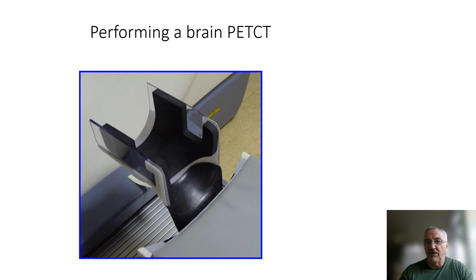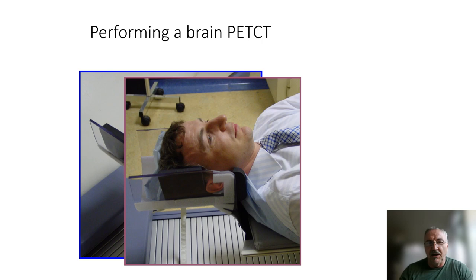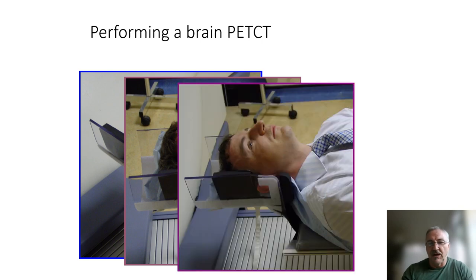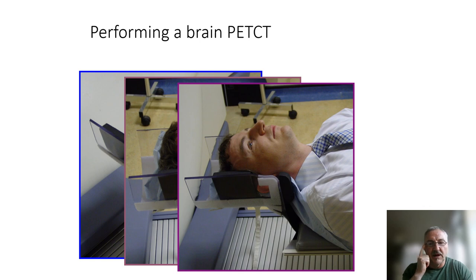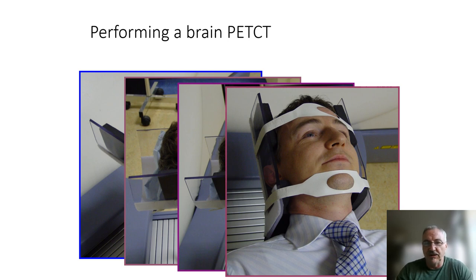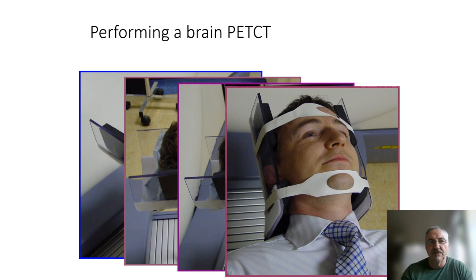We use a headrest. You place the patient in the head holder and try to get a formal positioning where the external meatus and the outer canthus of the eye are in the vertical plane. You can use lasers to help with that. Then we want some kind of simple restraint — not a clamp, these are simple to remove, just velcro straps. It gives people something to feel so that they can keep their head still for the 10 to 15 minutes of acquisition.